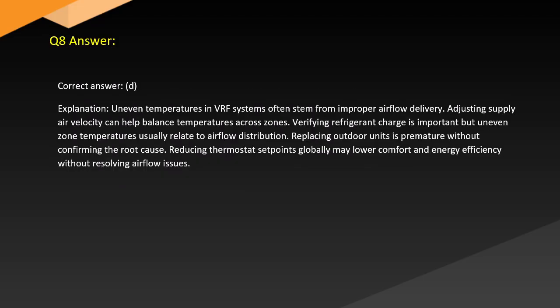Answer. Correct answer: D. Explanation. Uneven temperatures in VRF systems often stem from improper airflow delivery. Adjusting supply air velocity can help balance temperatures across zones. Verifying refrigerant charge is important, but uneven zone temperatures usually relate to airflow distribution. Replacing outdoor units is premature without confirming the root cause. Reducing thermostat set points globally may lower comfort and energy efficiency without resolving airflow issues.